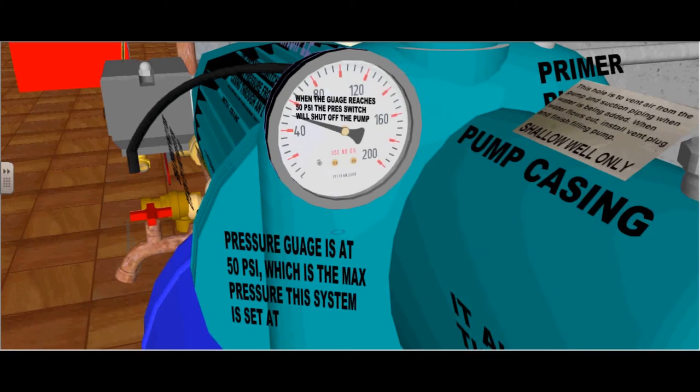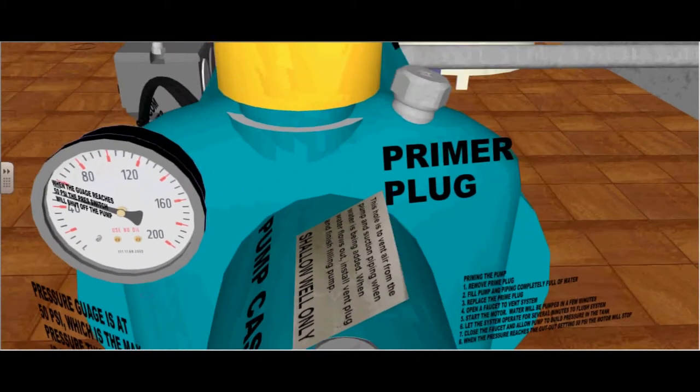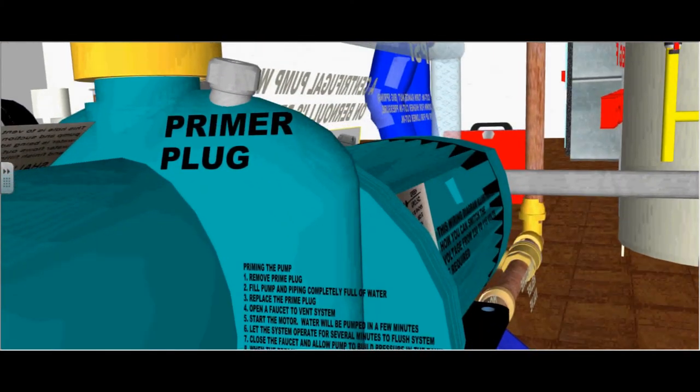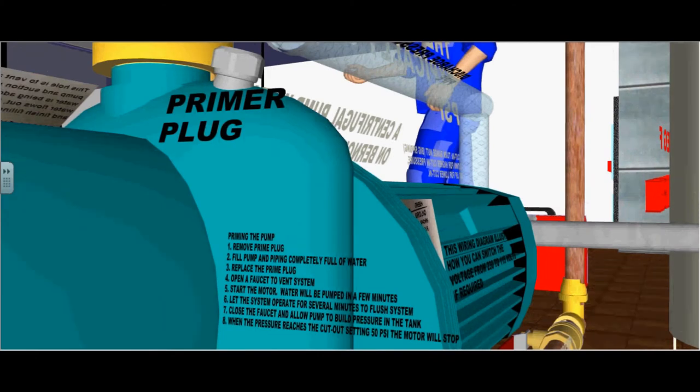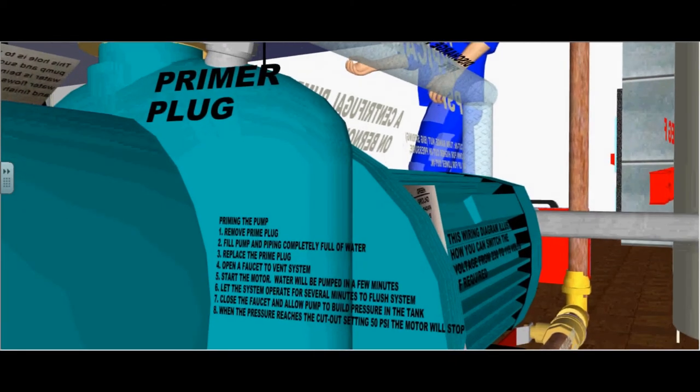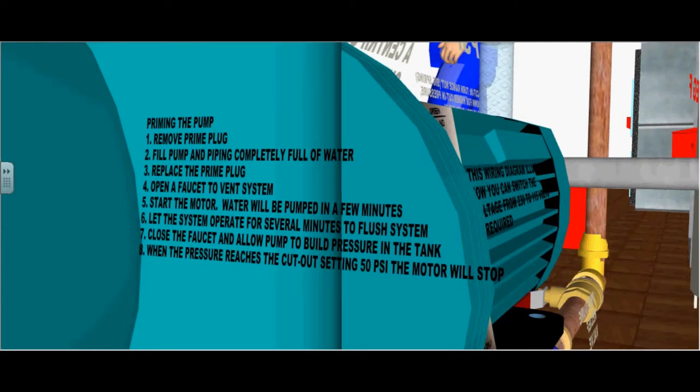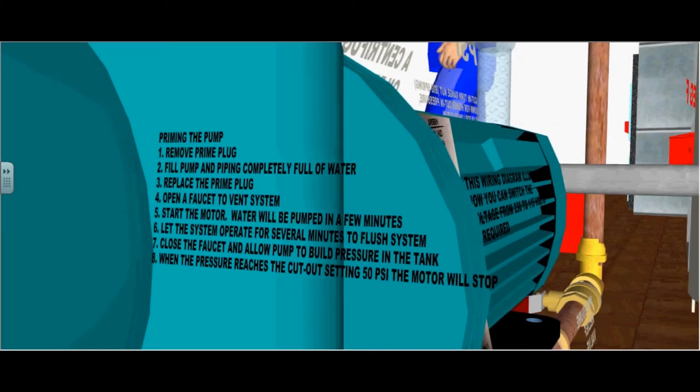The pressure gauge is set at 50 psi, which is the maximum pressure this system is set at. Here is the prime plug. To prime your pump on new installation, you remove the prime plug. You fill the pump and pipe completely full of water. Replace the prime plug. Open a faucet to vent the system. Start the motor. Water will be pumped in a few minutes. Let the system operate for several minutes to flush the system.